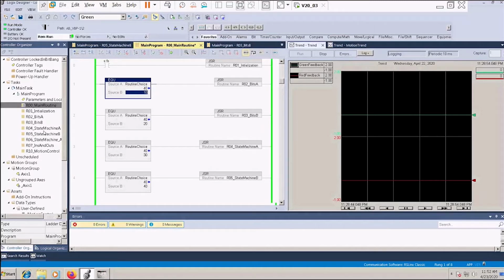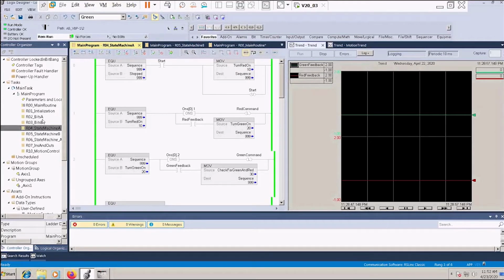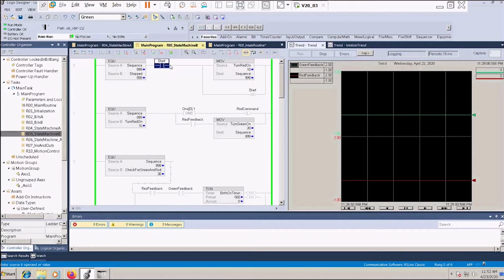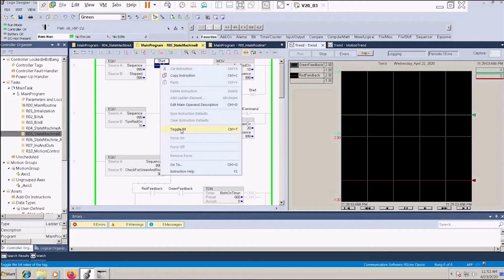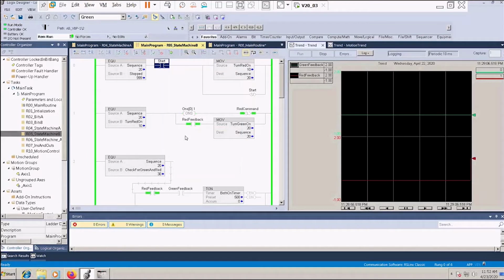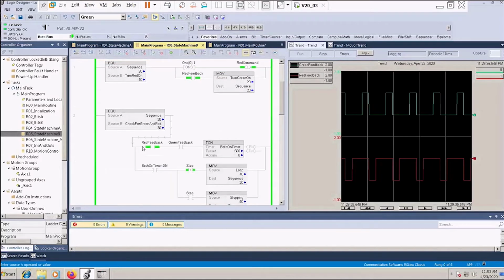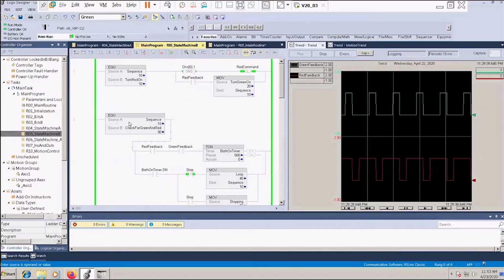So, 2 different ways. The original produced the same waveform as bits A. The second one, fire him up with a different order of scan, not necessarily order of operations, and we get the original waveform. So the point of that is the orderly control of your program regardless of which order the code is executed in. Because the state machine is still sequencing through 10, 20, 30, it's now, oh, well, it's rung 0, then rung 2 does its thing, and then we flip back. Well, excuse me, rung 1, then rung 3, flip back to rung 2.